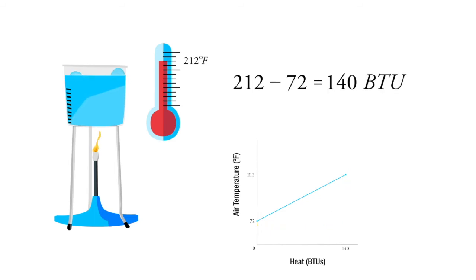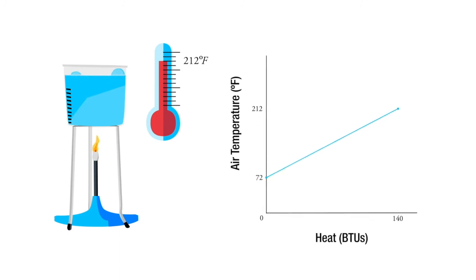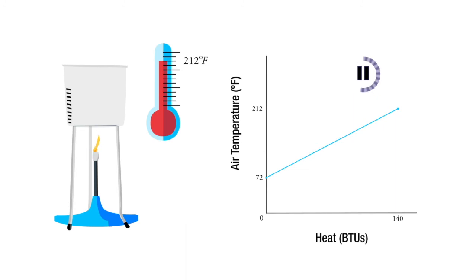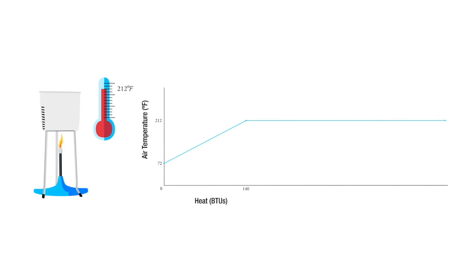If we take that same pound of water and we change it from 212 degrees of water and we're going to boil it, so we're going to change it to 212 degrees steam, how many BTUs is that going to take? Go ahead and take a guess. Hit pause and just take a guess. It's pretty remarkable because where it only took 140 BTUs to take water from room temperature to the boiling point of water, changing state from water to gas requires 1,061 BTUs for that pound of water.